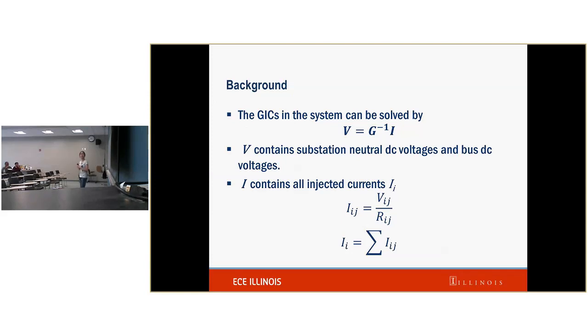So first, the GIC can be calculated by first obtaining the voltage of all the nodes in the system, using the equation V equals G to the power minus 1 times I, where V contains the substation neutral DC voltage, and I contains all the injected current. To calculate the injected current, we...